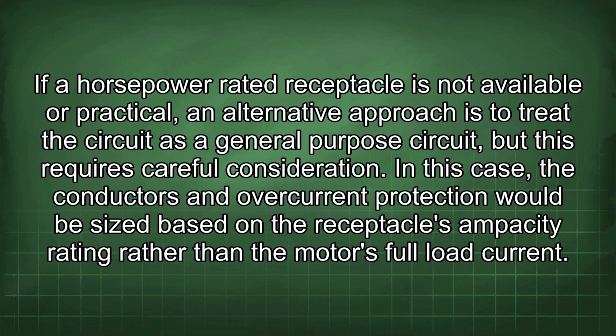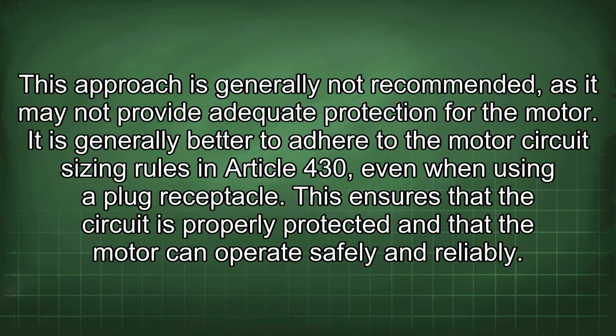If a horsepower-rated receptacle is not available or practical, an alternative approach is to treat the circuit as a general-purpose circuit, but this requires careful consideration. In this case, the conductors and overcurrent protection would be sized based on the receptacle's ampacity rating rather than the motor's full load current. This approach is generally not recommended, as it may not provide adequate protection for the motor.